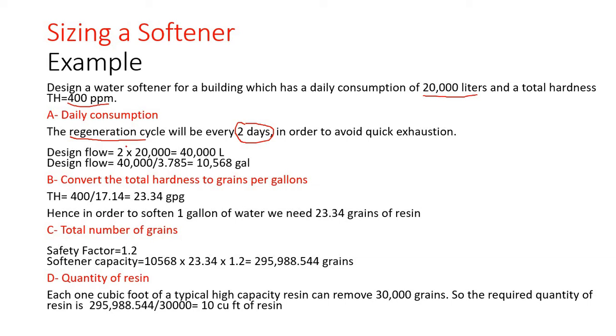Therefore, the design flow rate will be doubled — times two — and we will design for 40,000 liters. We will then convert it to gallons, and we will get 10,568 gallons.